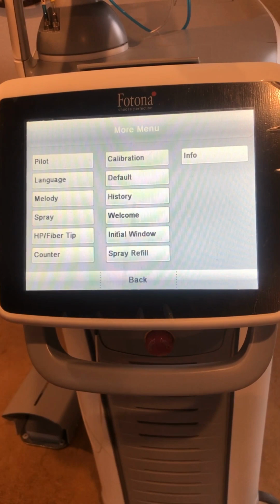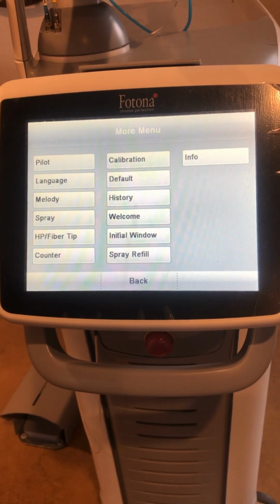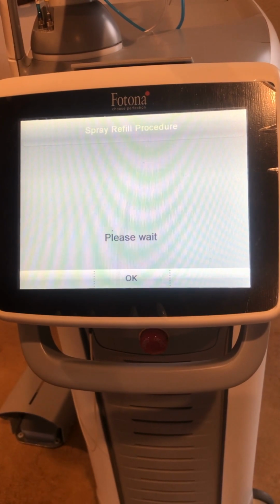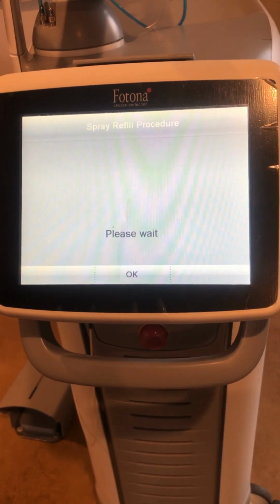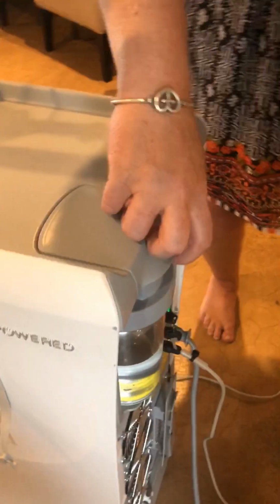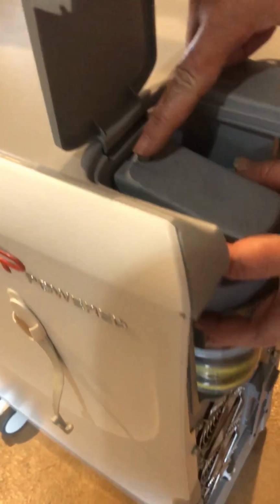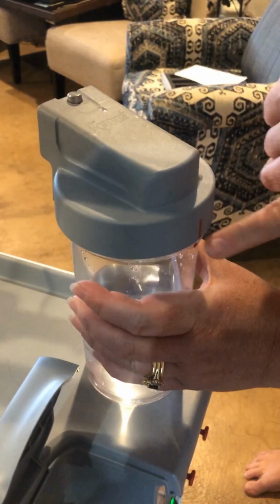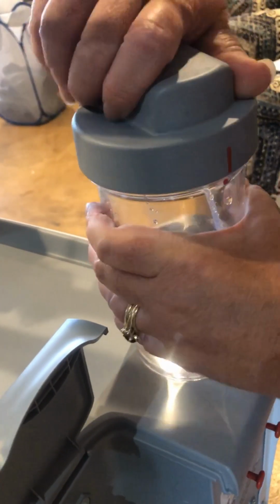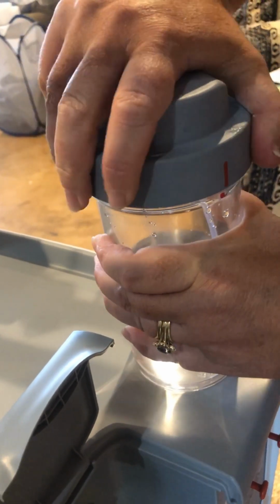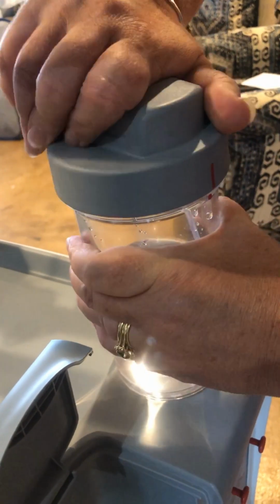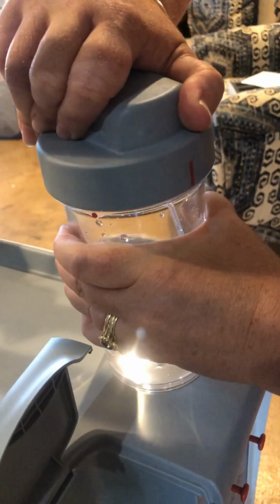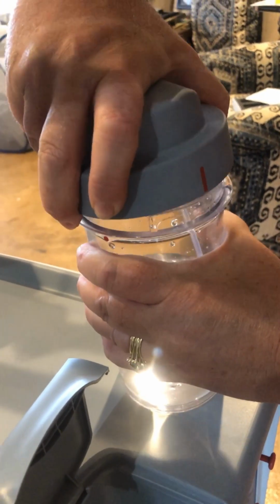And then for spray refill, let's say the water level got low enough that you need to refill. You're going to come to this More button and hit spray refill, and now it's going to decompress the unit. And then from there, you're going to come around to the back of the machine. You're going to lift up here, and this is a quick disconnect. You just push right here and pull straight out. Use something to stabilize you, but you can see the circles and the line on this. Usually wait a few seconds so that it decompresses, and then turn it between one of those circles and lines, and then start to pull straight up.